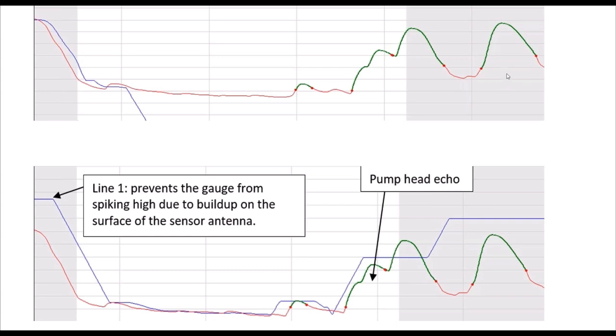Right? What happens is when you close that metal lid and you raise your level up above 60%, there is so much energy reflecting off that lid that it begins to replicate itself. So what's happening here is this big echo you see here is a multiple echo of this echo here. Now what happens to the sensor?